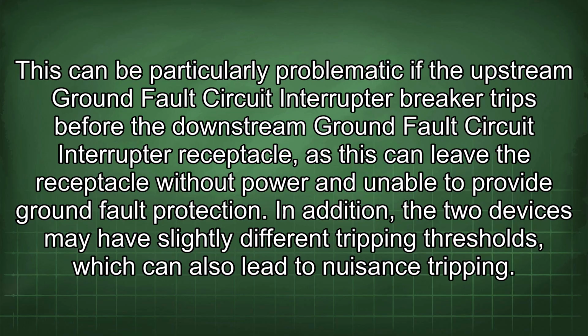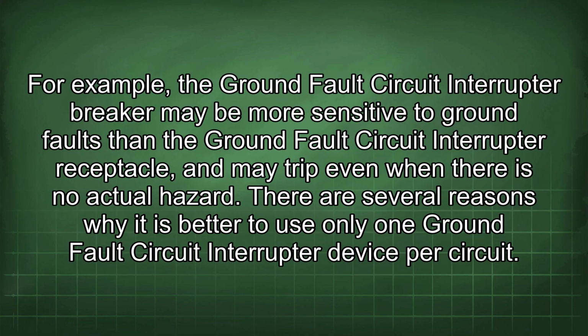In addition, the two devices may have slightly different tripping thresholds, which can also lead to nuisance tripping. For example, the ground fault circuit interrupter breaker may be more sensitive to ground faults than the ground fault circuit interrupter receptacle, and may trip even when there is no actual hazard.